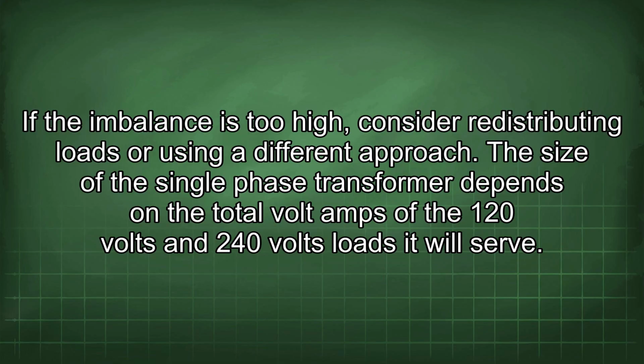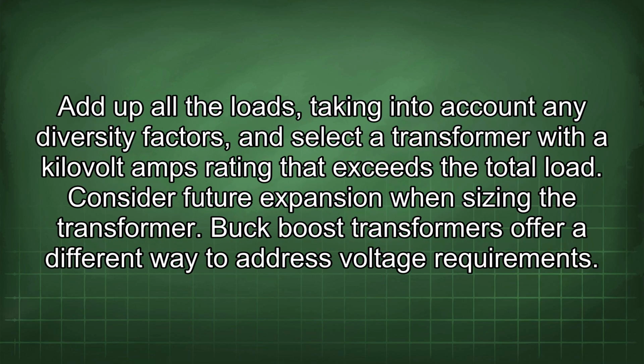The size of the single-phase transformer depends on the total volt-amps of the 120 volt and 240 volt loads it will serve. Add up all the loads, taking into account any diversity factors, and select a transformer with a kilovolt-amps rating that exceeds the total load. Consider future expansion when sizing the transformer.